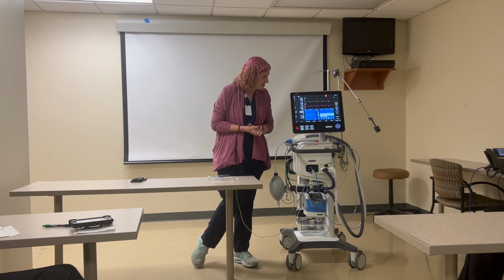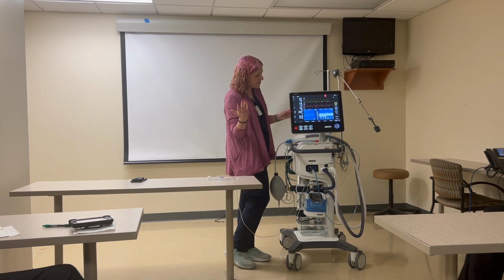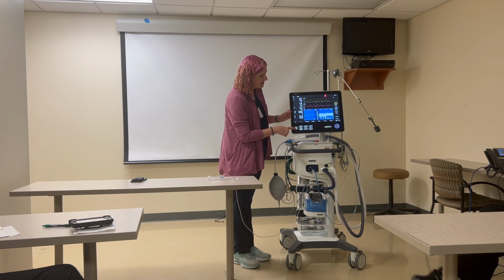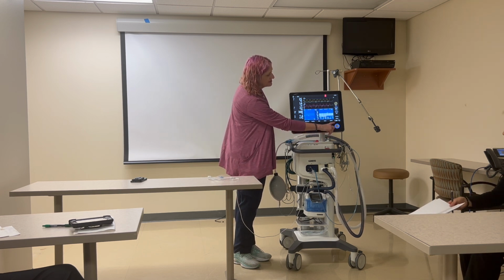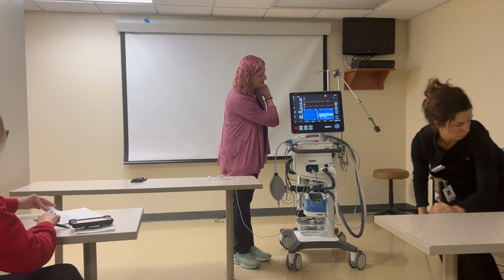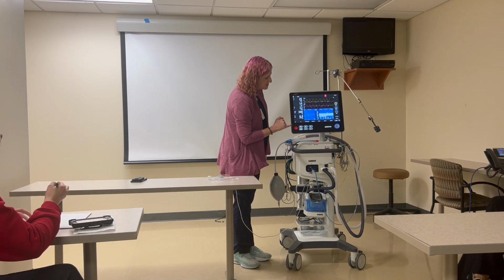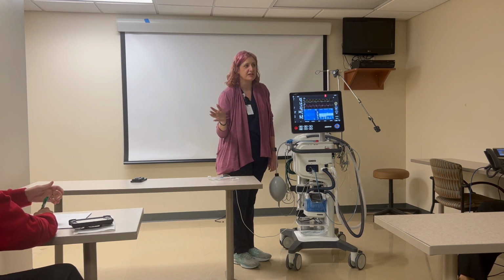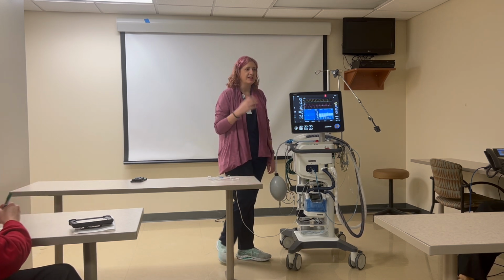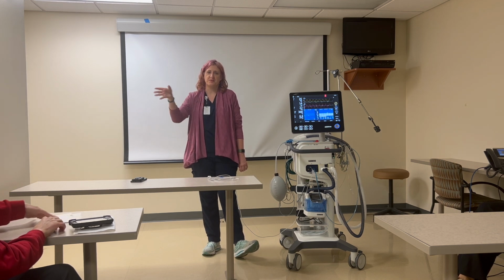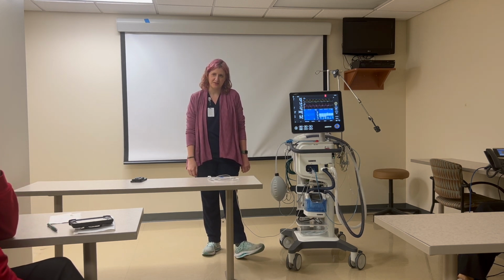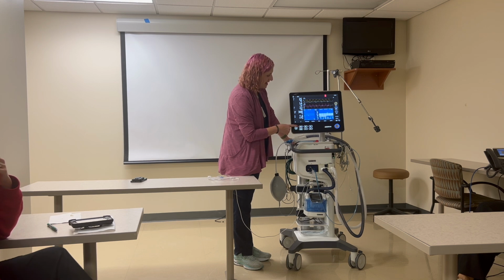But coming down to our buttons, regardless of the mode that you're in, the red silence button is telling you that your silence timer is activated. So our silence time is always going to be 2 minutes for our alarms. Just make sure that whenever you're getting ready to leave the room, you hit this button again, activating those alarms, so that as soon as you walk out of the room, that patient doesn't pull that tube and self-extubate. Nobody knows when that happens.